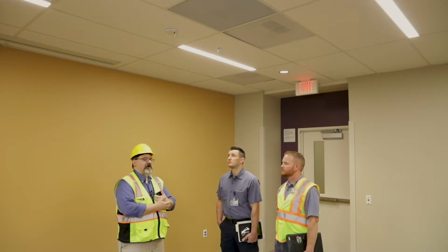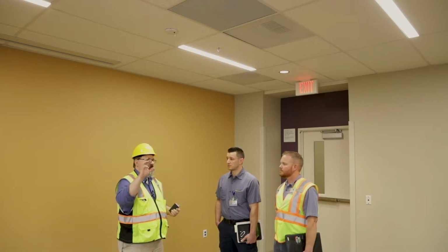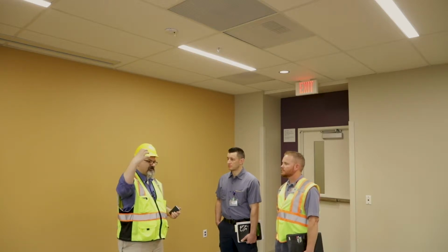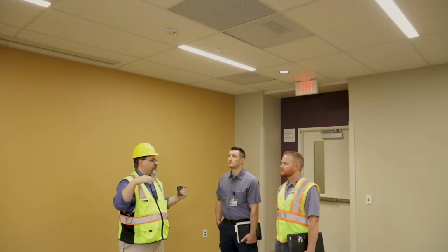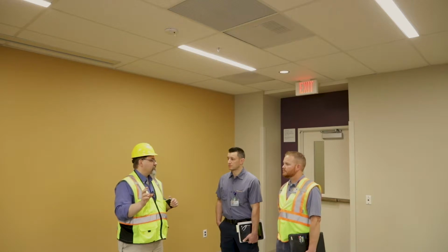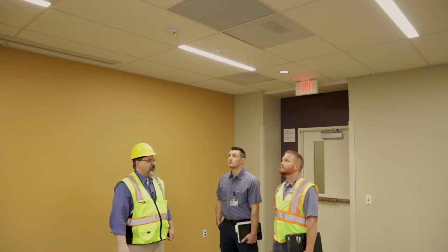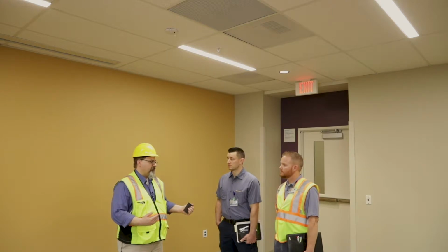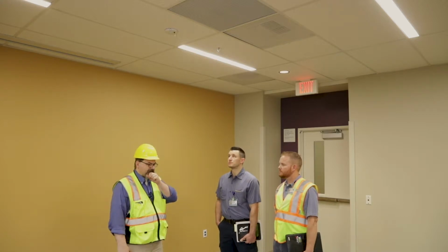Okay. All right, so dual technology, you know how that works. All of these devices, the switch on the wall, and the sensors inside the ceilings, usually near the doors, is where they've put them. On a J-box, there's a room controller that's installed. And all these things are connected by Cat5, and they have indicators on them that show whether or not they're powered on. With the sensors, we even have an error code, so you can tell the guys, hey, I've got error 08, and it indicates something on the sensor, and they can diagnose it, essentially. Most of your issues will be from Cat5 getting unplugged, from somebody being in the ceiling or something like that.